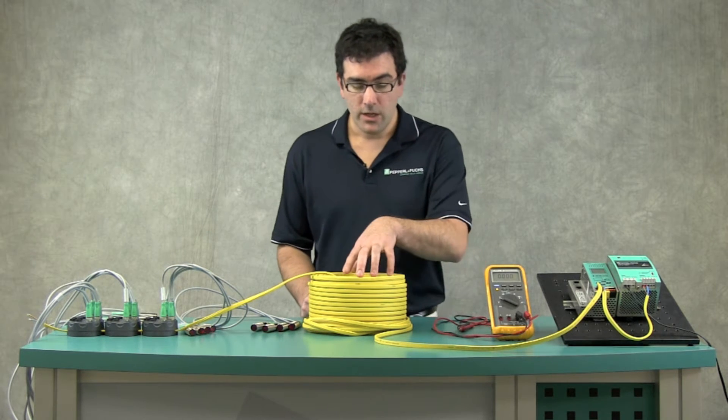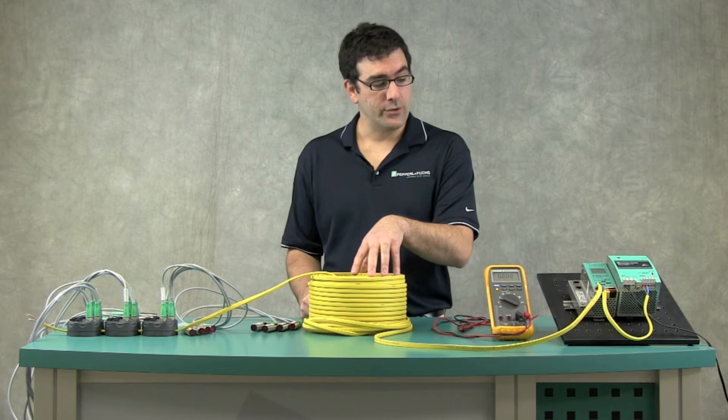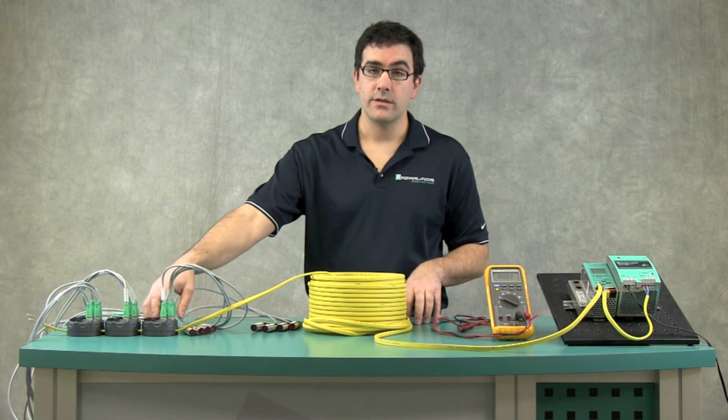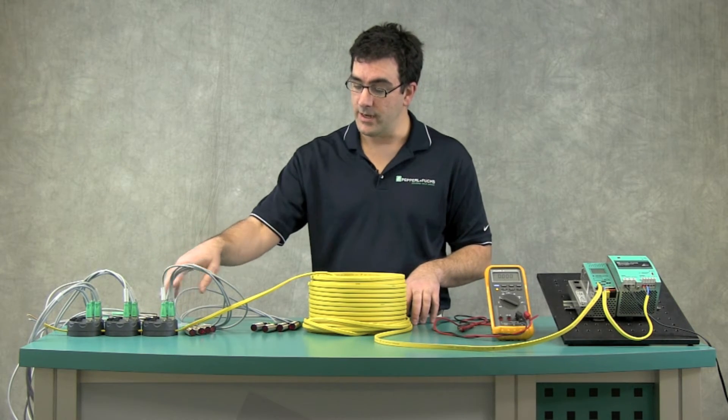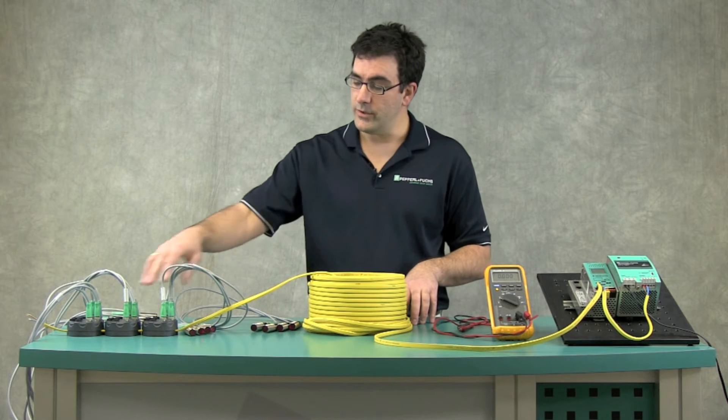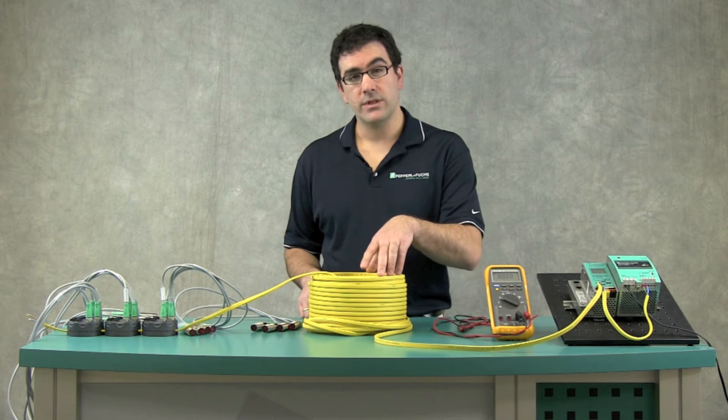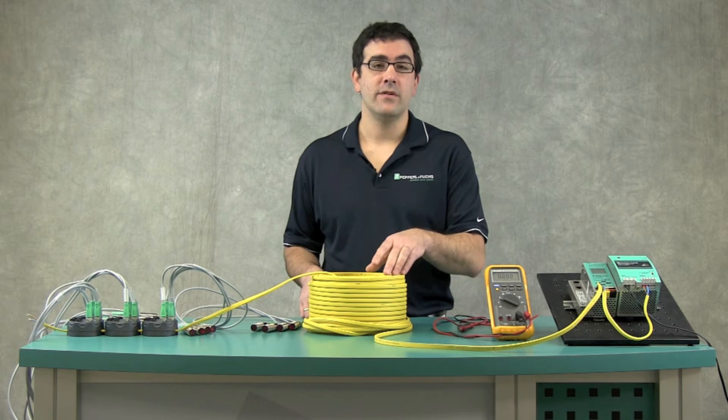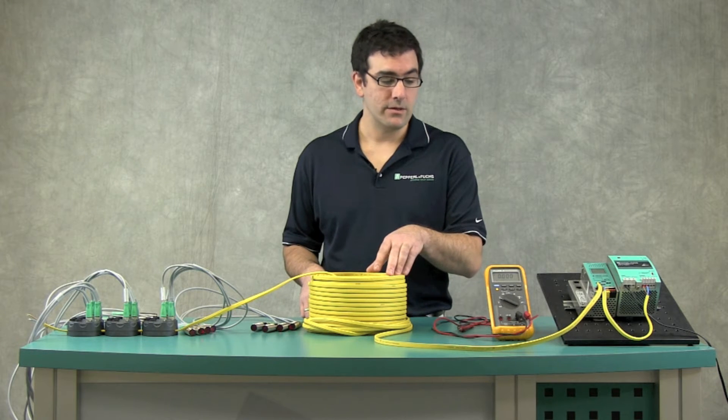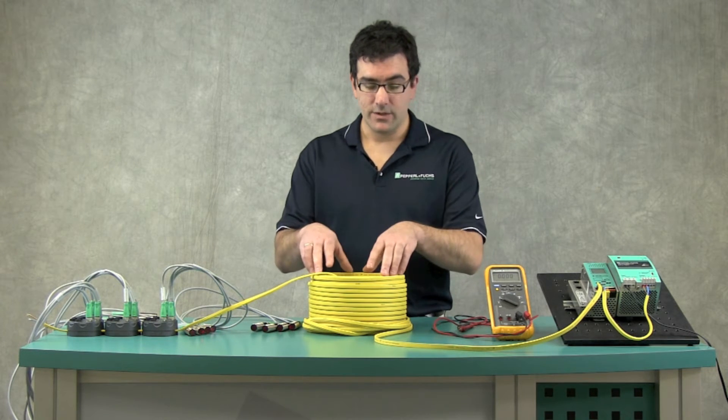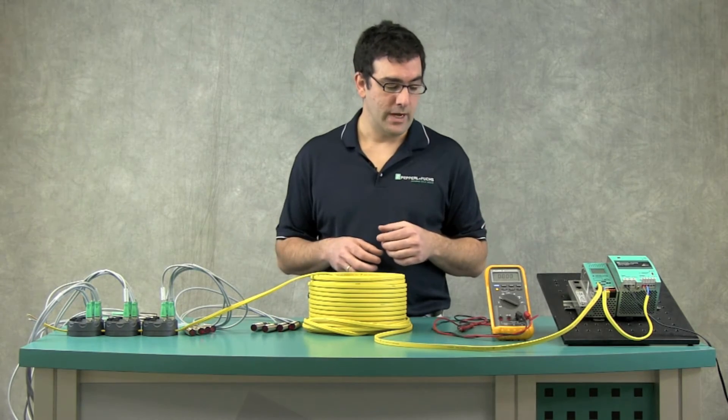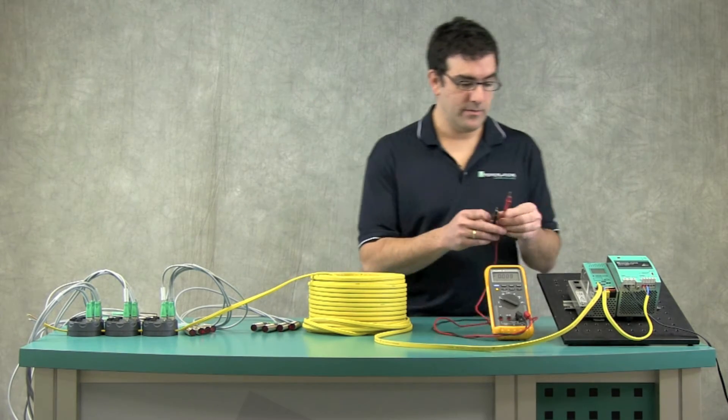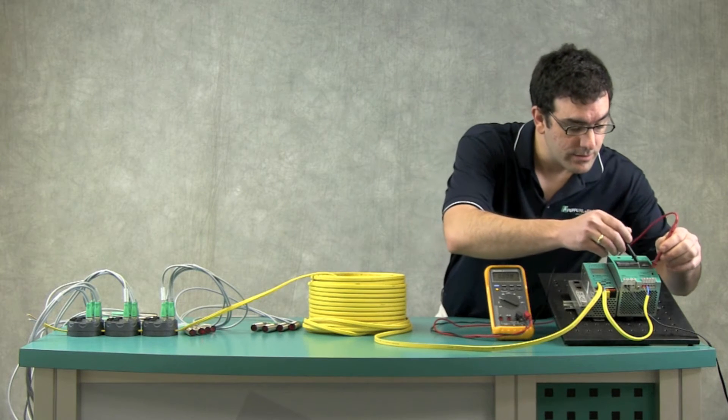So, what we typically do to calculate the voltage drop, we know the current, which is about 330 milliamps for this setup, 12 sensors, 3 modules, and we know the resistance of the cable, which is about 13.5 ohms per 1,000 meters. If we take those calculations, we'll notice we've got about a 0.8 volt drop. So let's measure that now just to see if we're close.